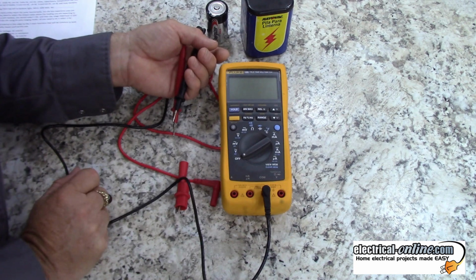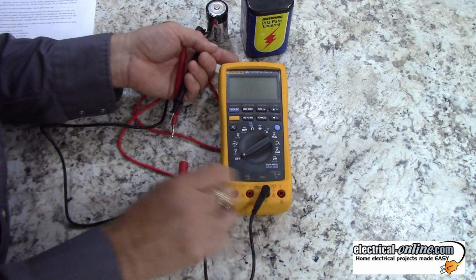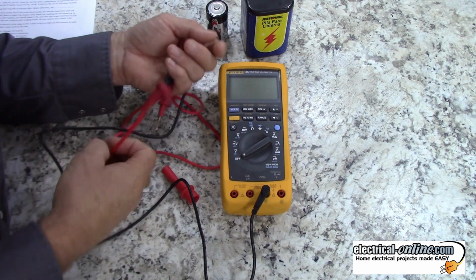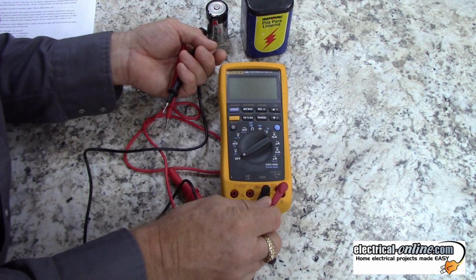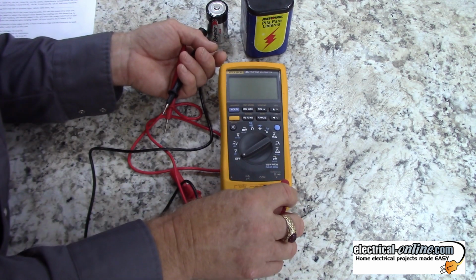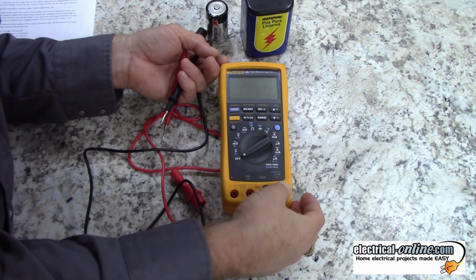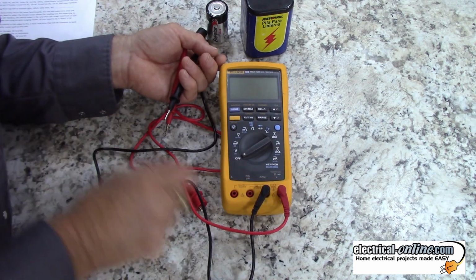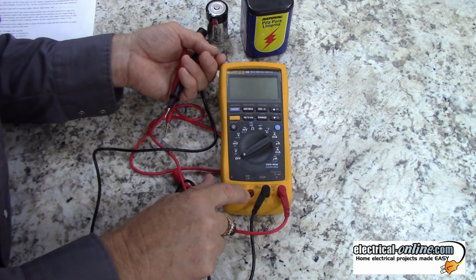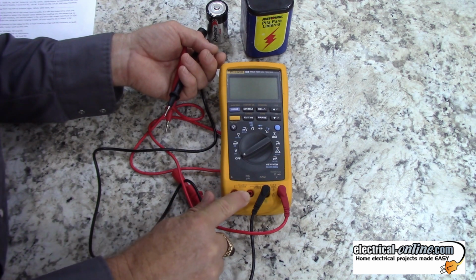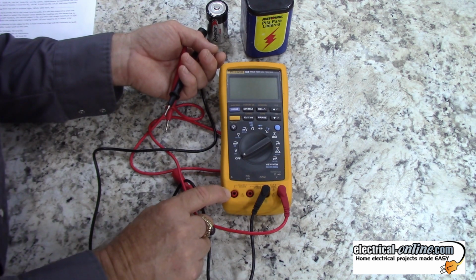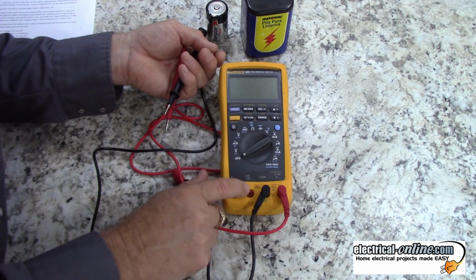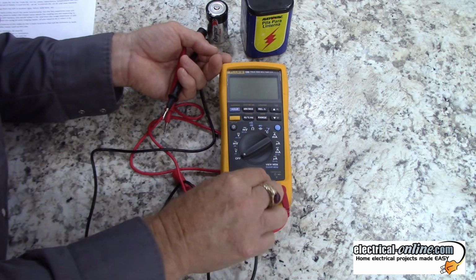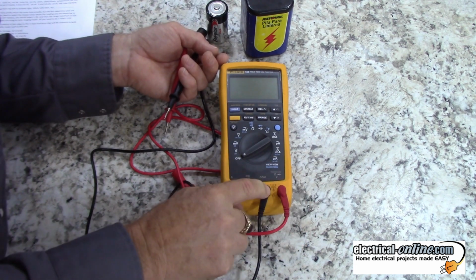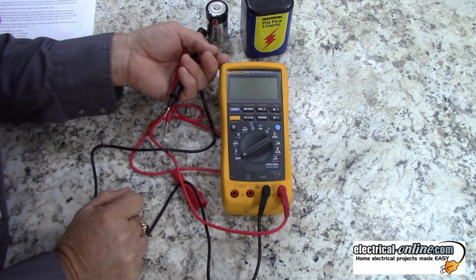Now for voltage testing, I'll give you a close-up look. For anything up to 1,000 volts, your red lead goes in here. The other terminals include a 400 milliamp fused terminal and a 10 amp fused terminal for current testing, which we'll get into later. Right now we're on voltage, so the black lead goes into the common, and the red into the terminal marked volts.